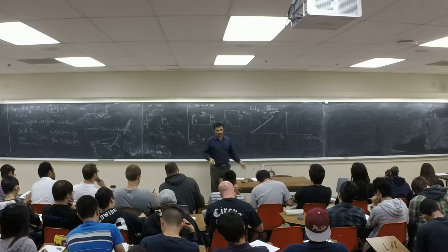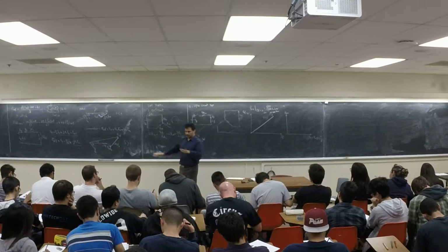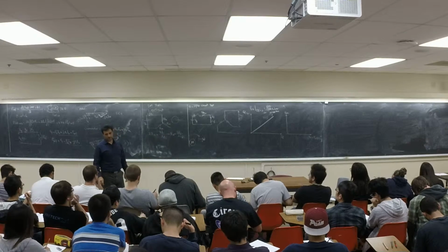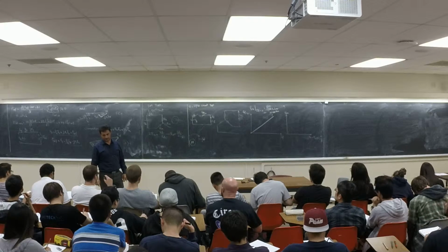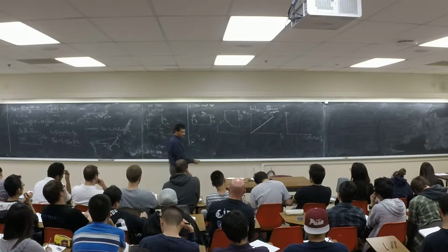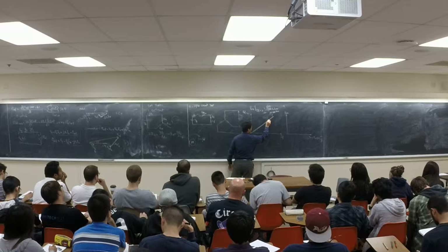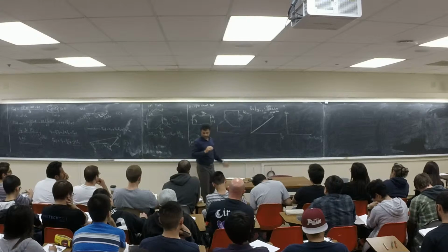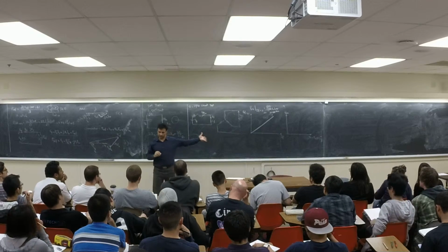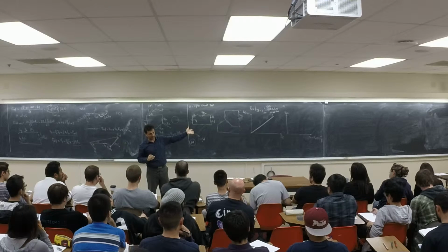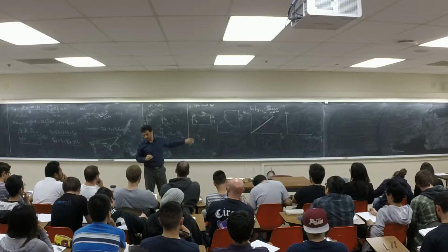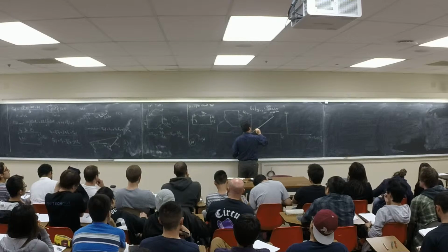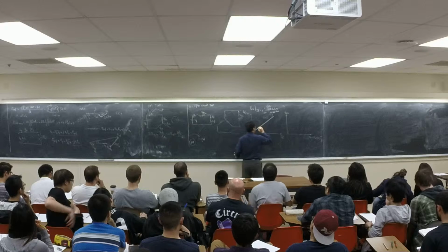This is the voltage that will be induced if everything is ideal and there is no saturation and no residual, right? What is going to happen in reality? First of all, we are not going to start from 0. We are going to start from a little bit above 0, for example here. This is kind of exaggerated, but I just want to show you the difference. We're going to start above 0 because there is some residual flux, right? So what is going to happen up to some point is going to be like this.